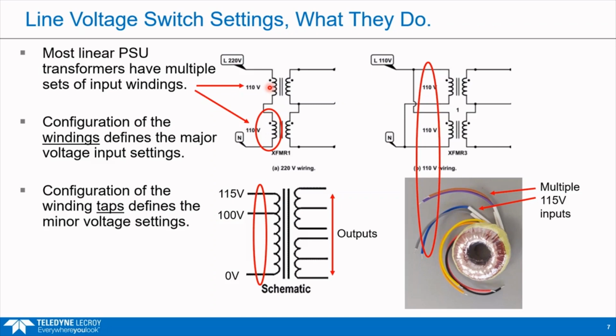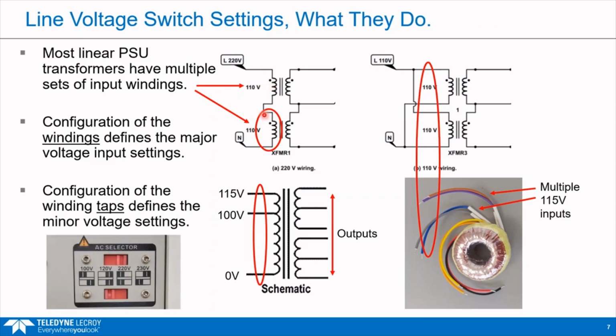With the switches, some switch the main windings and others switch the taps. Looking at our switch here, at the bottom it's thrown to the left, and that setting switches between series and parallel - currently set to series, and thrown right it would match these and set parallel. So this switch sets whether the main windings are in series or parallel, while the upper switch sets the fine level, between 100 and 120, or 220 and 230, adjusting taps rather than windings for finer granularity. That's how it works.